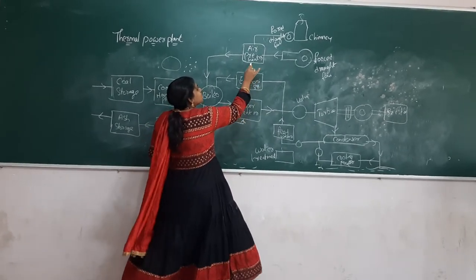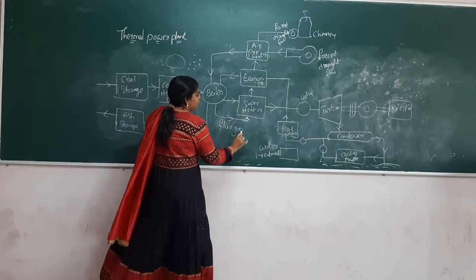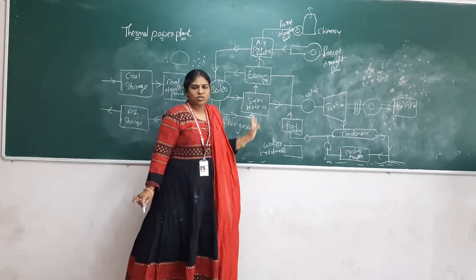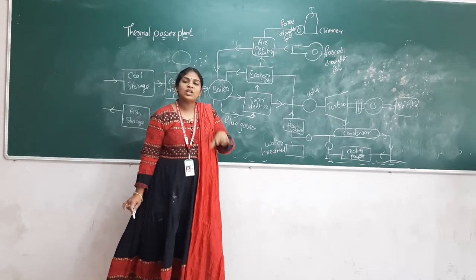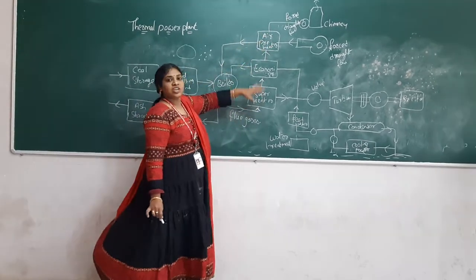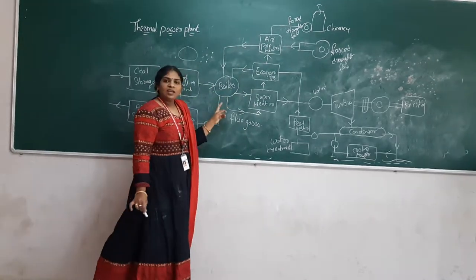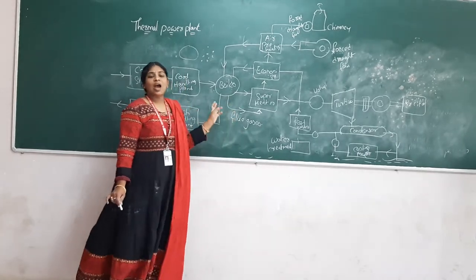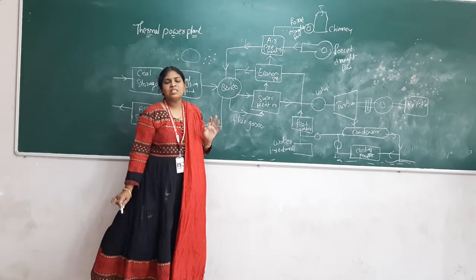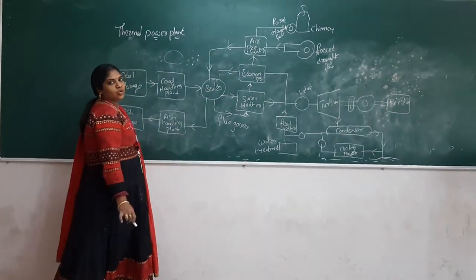There are three main blocks: superheater, economizer, and air preheater, and there is a common link between them — flue gases. After combustion of coal, you get different flue gases which need to be expelled into the atmosphere. But these flue gases consist of high temperature, so at every stage before the flue gases go to the atmosphere, we utilize their heat. Then we send them to the chimney. We also get ash after combustion, which has to be removed periodically — if not removed properly, it reduces boiler efficiency. The ash is removed and goes to ash storage.